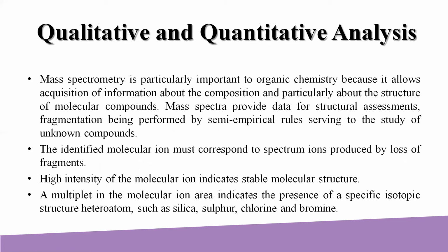The proportionality of the intensity of the signal with the analyte amount allows the use of mass spectrometry in quantitative assays. For this purpose, internal standard methods are used. As a standard, a compound similar to the analyte is employed, provided that the ionization produces easily monitored ions different from those of the analyte. Similar chemical compounds, such as a deuterated isotope or analog, whose ionization produces easily monitored ions different from those of the analyte, can be employed.